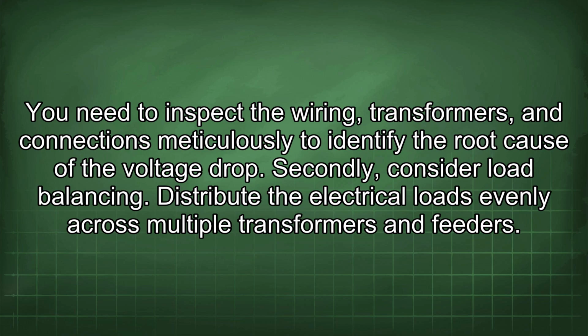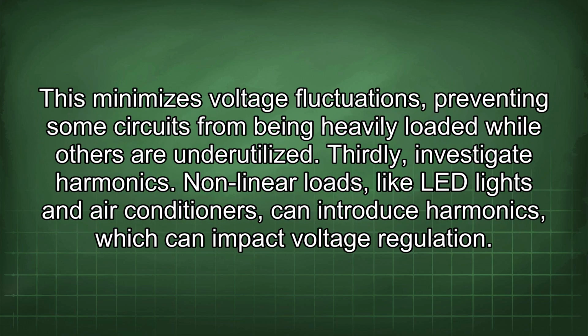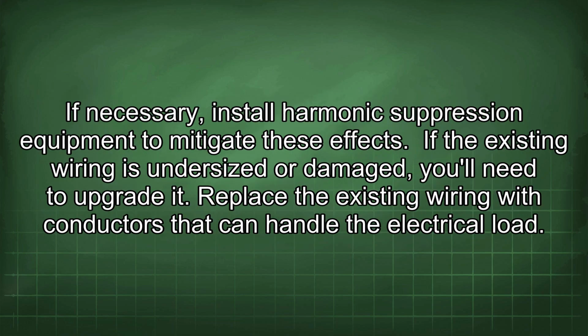Secondly, consider load balancing. Distribute the electrical loads evenly across multiple transformers and feeders. This minimizes voltage fluctuations, preventing some circuits from being heavily loaded while others are underutilized. Thirdly, investigate harmonics. Nonlinear loads, like LED lights and air conditioners, can introduce harmonics, which can impact voltage regulation. If necessary, install harmonic suppression equipment to mitigate these effects.